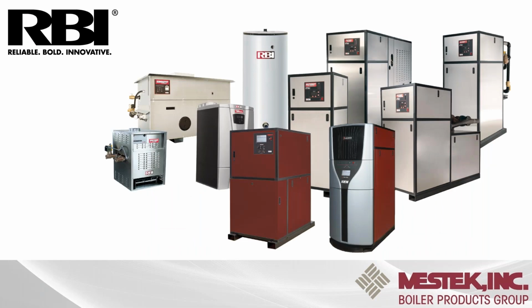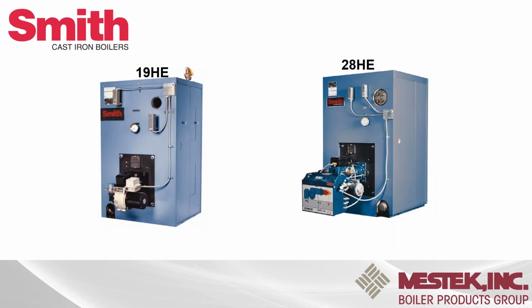So the other company is RBI, and RBI started off as a copper fin type water heater boiler product. Those sizes currently range from around 500,000 up to 10 million BTUs. We have now moved into the condensing high efficiency stainless steel products, which range from 199 up to 6 million BTUs, offering water tube and fire tube products that can be used for water heating on the water tube side and boiler, and on the fire tube side, it's boiler only. And lastly, Smith Cast Iron. This is our sectional cast iron boiler that can be used for hydronic systems and low pressure steam systems.